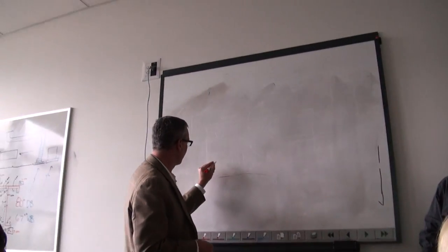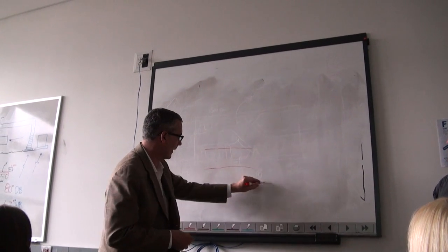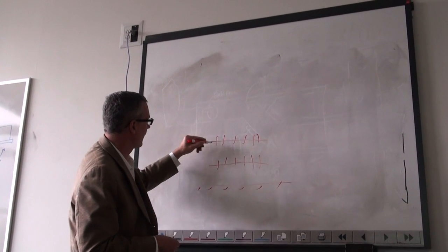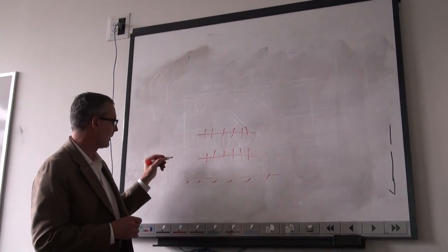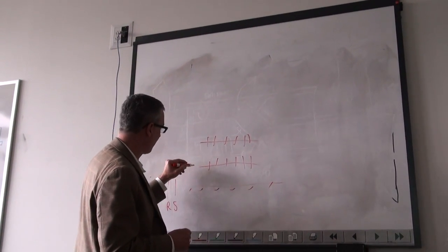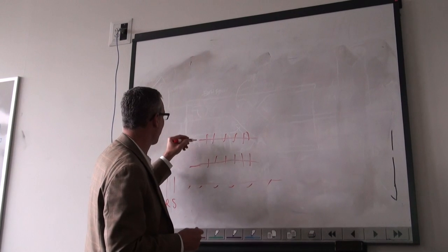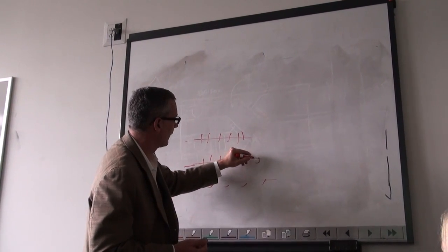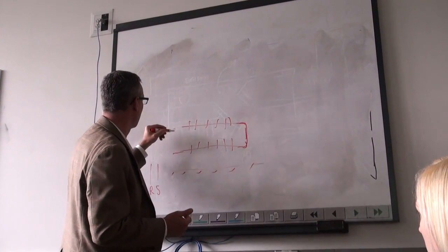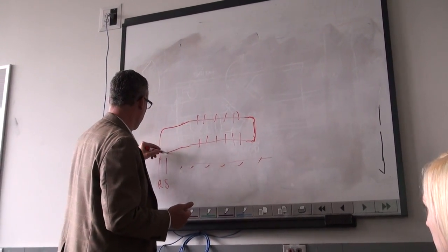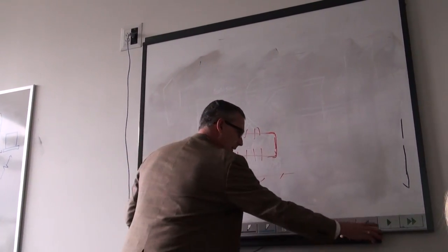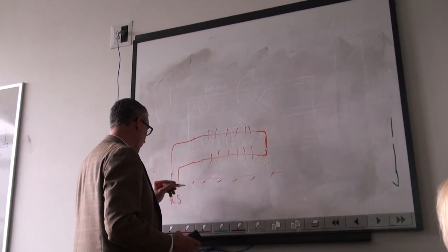Fin tube. So you've got two tiers. Here's the ground, right? And here's your fins. And a contractor, if you don't tell them and say you're bringing supply and return to the same side, is going to come in this side with either top or bottom. He doesn't care. He doesn't know. He's going to put a 90, a little piece here, another 90, and come right back through this. You know why? It's cheaper. So he will not care one way or the other.